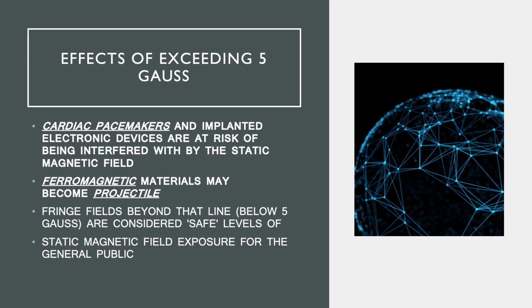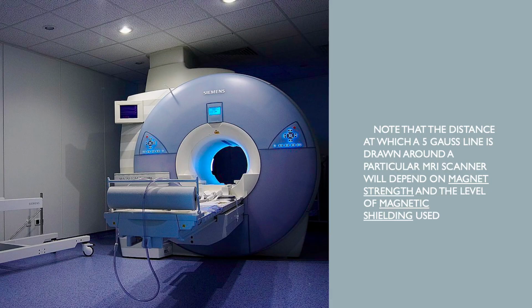Second, ferromagnetic materials may become projectiles. Note that the distance at which a 5 gauss line is drawn around a particular MRI scanner will depend on 2 factors. First, the magnetic field strength, and second, the level of magnetic shielding used. For our purposes, we consider the threshold of the magnet room door as the 5 gauss line. Electronic devices and ferromagnetic objects inside the 5 gauss line are strictly prohibited.